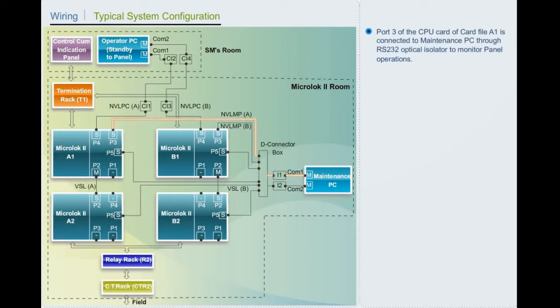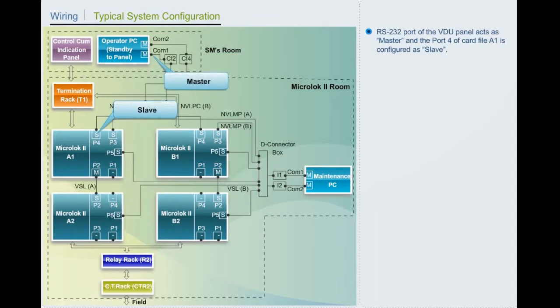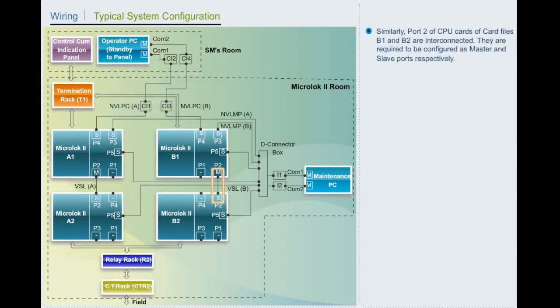Port 3 of the CPU card of card file A1 is connected to maintenance PC through RS-232 optical isolator to monitor panel operations. Port 4 of the CPU card of card file A1 is connected to the RS-232 port of the VDU panel through RS-232 or RS-485 converter cum isolator connected at either ends. RS-232 port of the VDU panel acts as master, and the port 4 of card file A1 is configured as slave. Similarly, port 2 of CPU cards of card files B1 and B2 are interconnected.